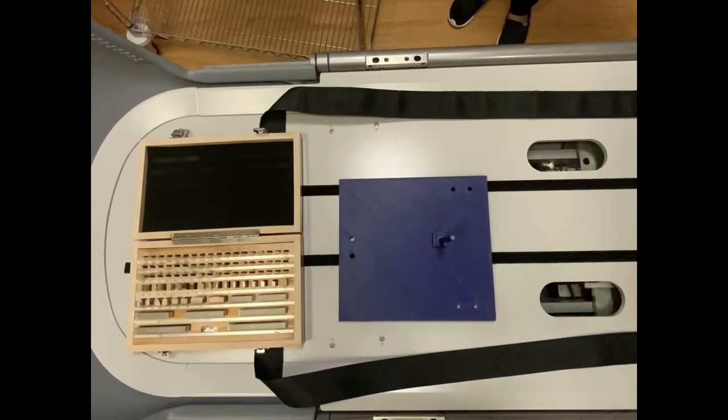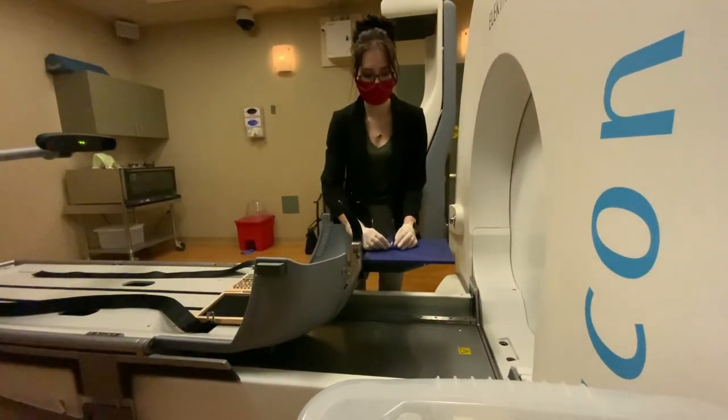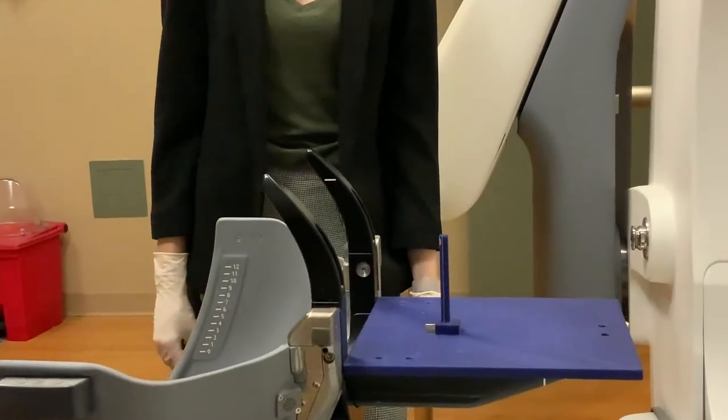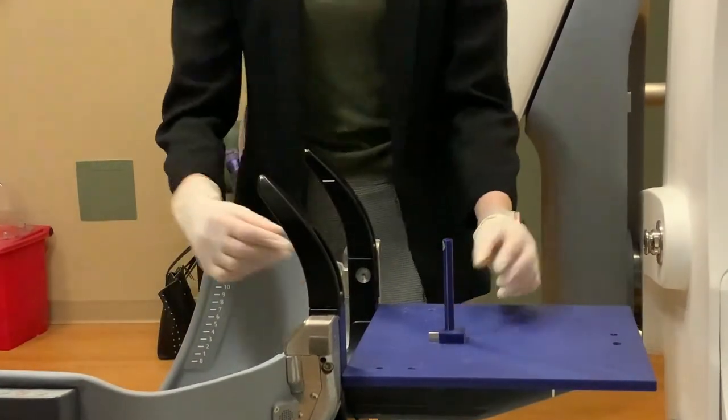Gauge blocks were used to set a standard distance and have accuracies of less than 0.4 micrometers. A gauge block is inserted in any of the X, Y, or Z directions and the HDMM system's measured shift is compared against the block thickness.